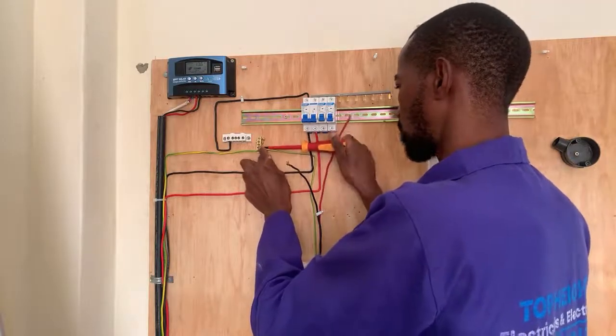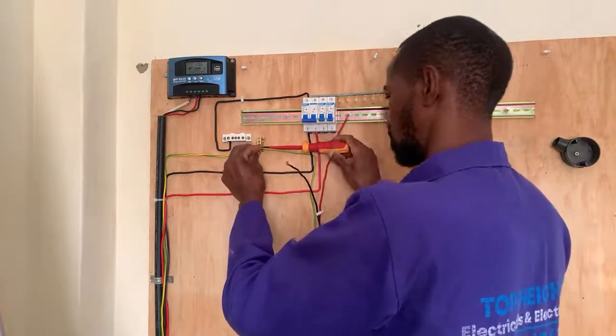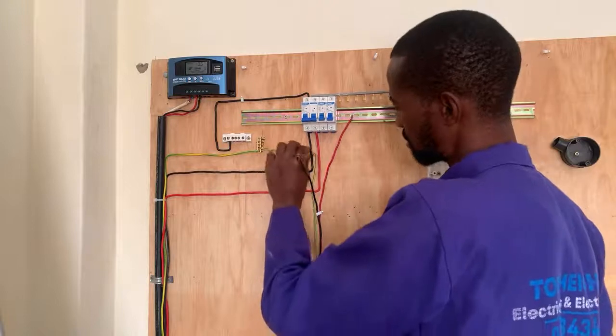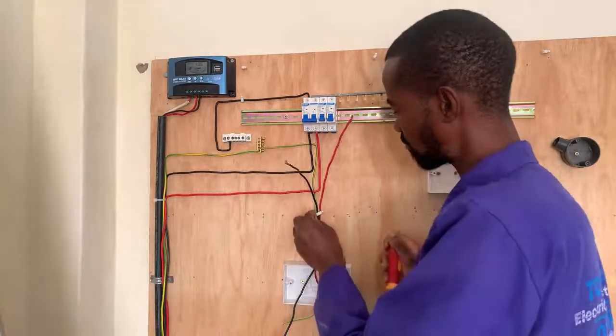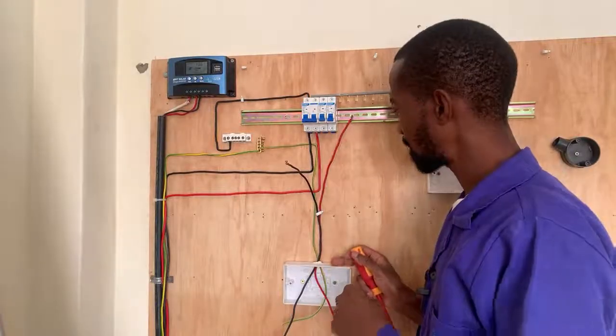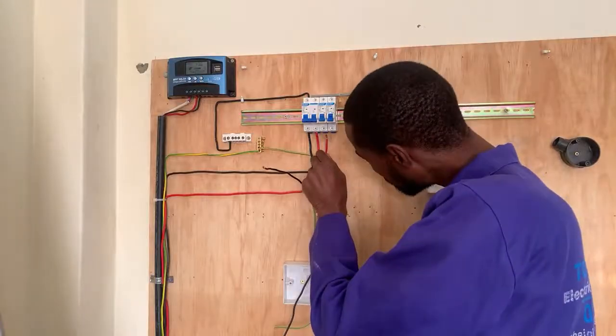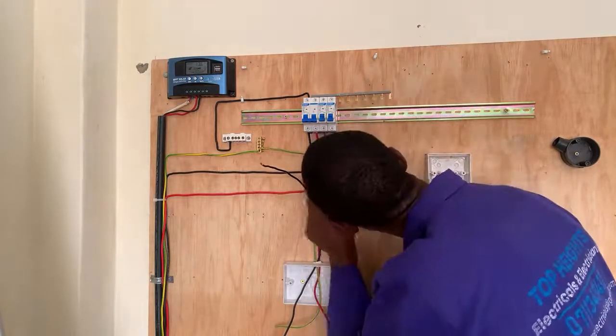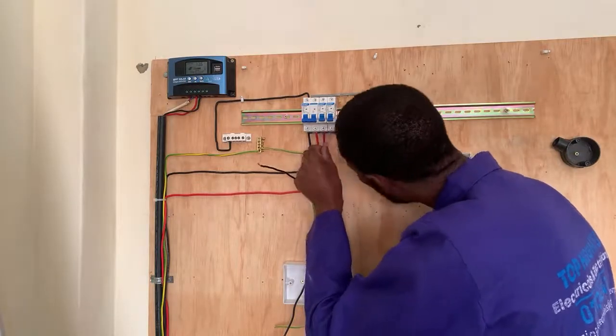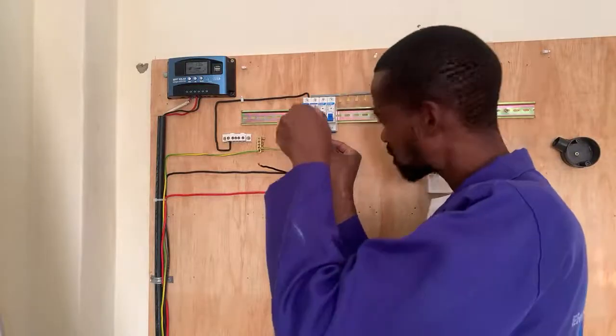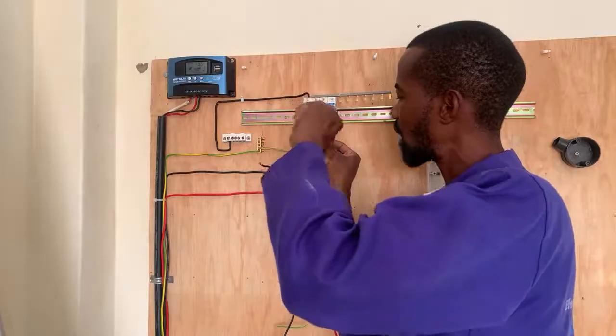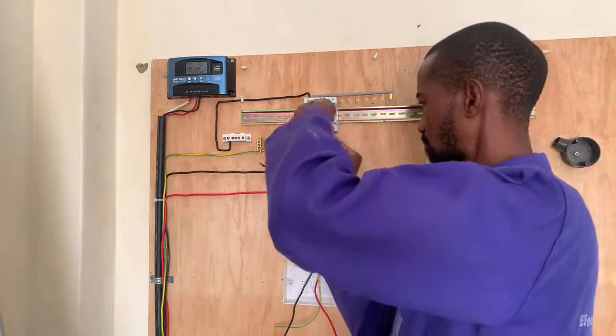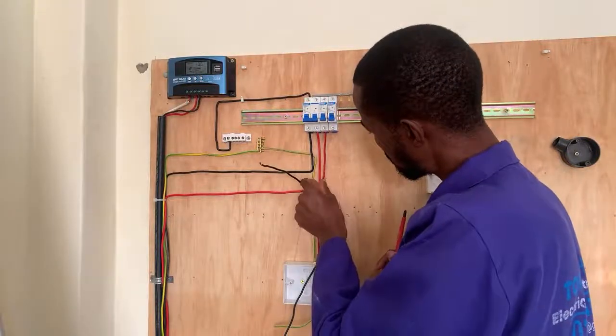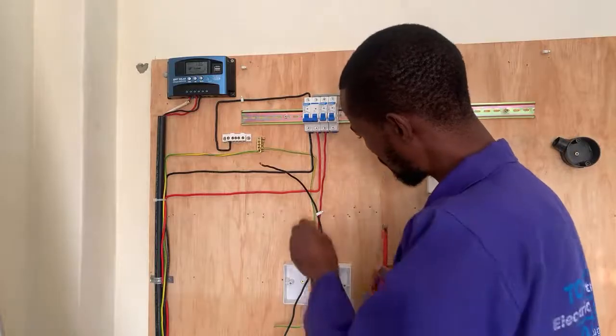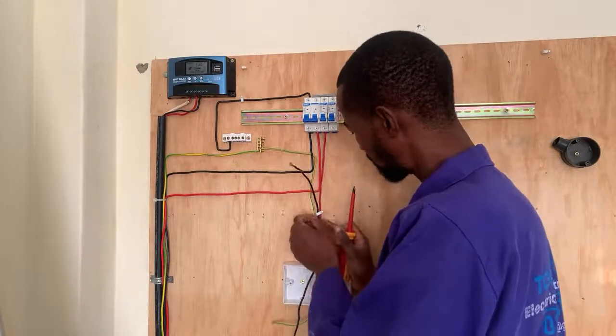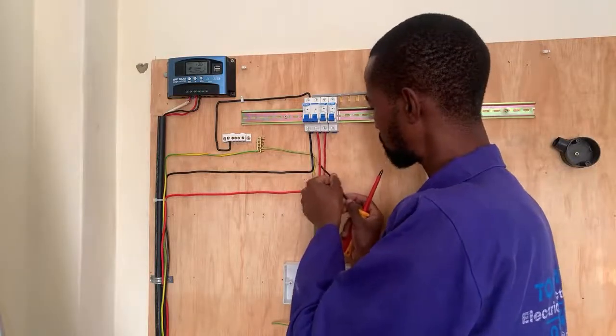Remember, our consumer unit is off. You can switch it off at the meter box or the meter board where there's a double pole. Let me connect this one here before it gets to touch the live connection. I'm connecting it to the 20 ampere MCB, making sure that connection or link is very tight. Remember, an electrical connection should be very sound as well as presentable or neat.